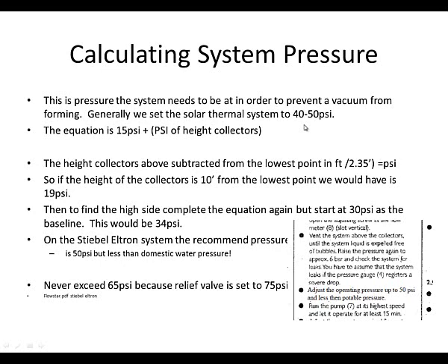So in that case, you would want to set the system pressure to 34 PSI. Now Stiebel Eltron recommends 50 PSI — the higher the pressure, the higher the boiling point for the fluid in the system. You could go as high as 65 PSI depending on the system, but since the manufacturer recommends 50 and our calculation gives 34 PSI, that gives you an idea of how to calculate system pressure.